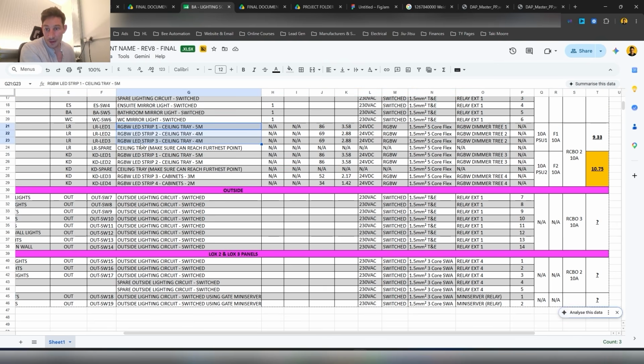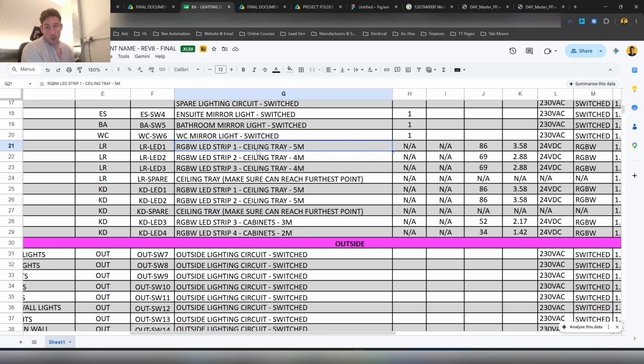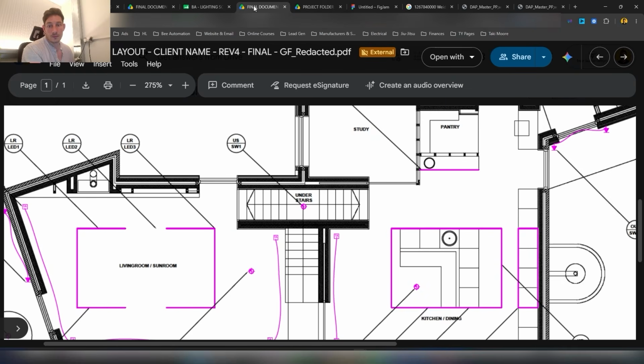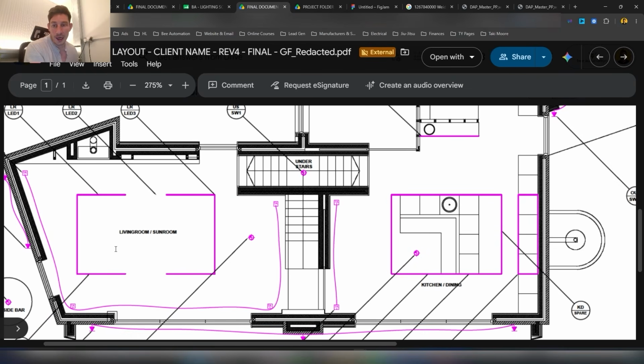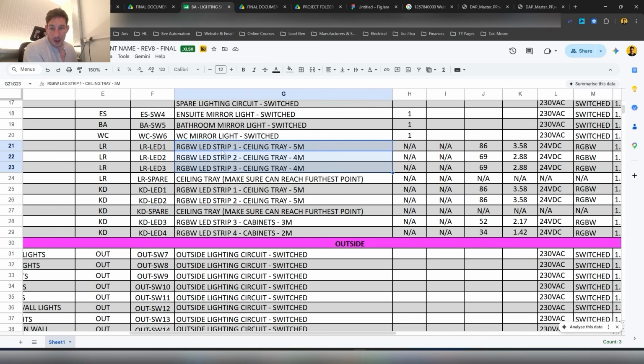If we zoom in a little bit, we've got three bits of separate LED strip, but they all make up the 13 odd meters of LED strip around the ceiling here. We're doing it from separate cable runs - you've got to do your voltage drop calculations and work out there's enough current carrying capacity in the cable, so you're not going to get voltage drop and whatnot. That's why it's done like that.